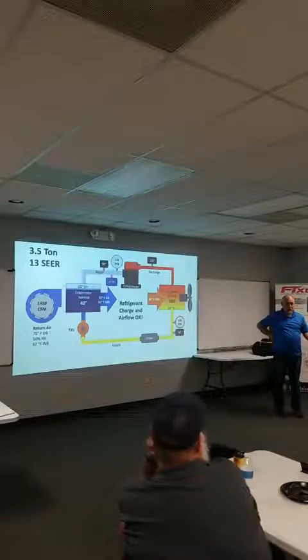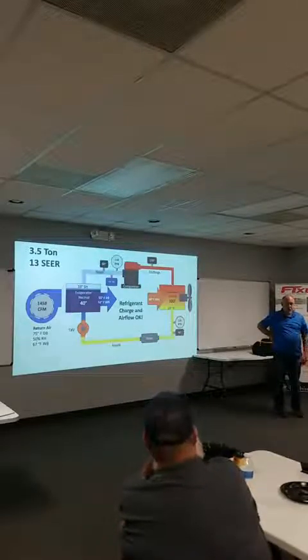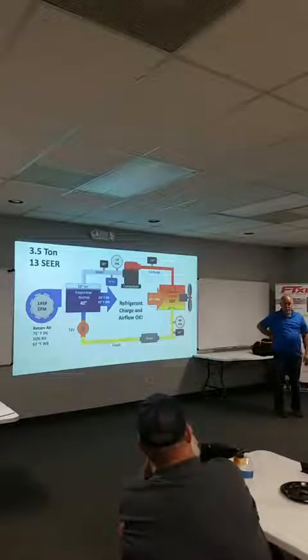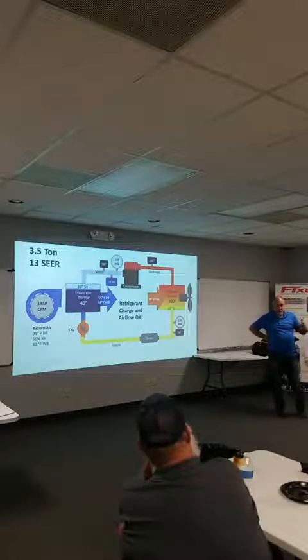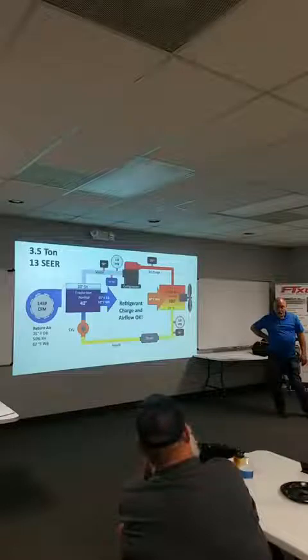So I started digging into it because I'm noticing that I'm getting just a crap load of oil back on the compressor. And thinking, well, a lot of compressor changes, maybe gotta drain some oil out because maybe the oil was washed down the evaporator and just never got back up. I don't know why it was returning that day, but it was. So I go downstairs and I try and measure the superheat of the evaporator. It's got an external equalizer line, connect the external equalizer to get the pressure, go over and measure the temperature. I'm like, I got no superheat. In fact, I feel the suction line and the suction line's warm. I go back upstairs and I measure it upstairs and it's like around 12 degrees of superheat. I'm like, how the hell am I getting superheat upstairs but not downstairs at the unit?